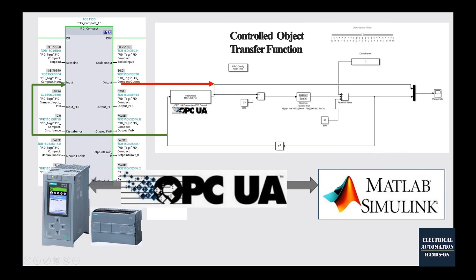As shown on the screen, this is the whole control loop structure. From the PLC side, we use PID Compact as our PID controller — that is our PID algorithm. This PID has an input and an output: the input comes from the MATLAB Simulink feedback, and the output is our PID control signal, which is sent into MATLAB Simulink. The communication between MATLAB and the PLC uses OPC UA, which allows MATLAB Simulink to directly communicate with the PLC without any interface software.